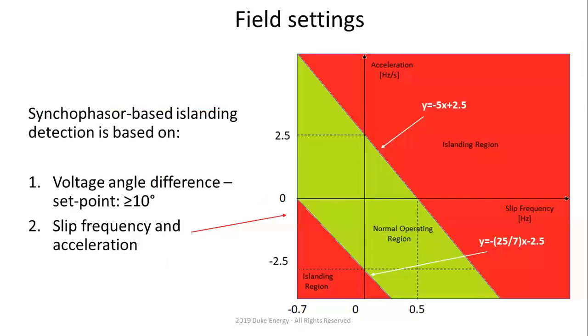Field settings are based on two things. There's a voltage angle difference, for which our set point was greater than 10 degrees. And then there's a slip frequency and acceleration. For those of you who might not have seen this, slip frequency is the rate of change of voltage angle, and the acceleration is the rate of change of slip frequency. So you have this voltage angle difference set point, and then you have the screen on the right side.